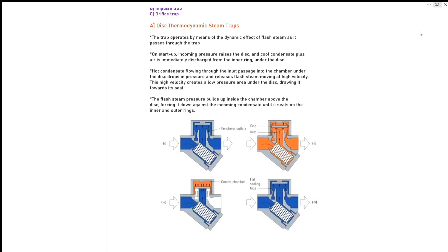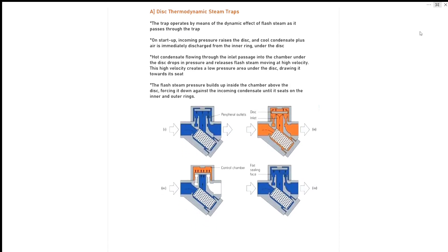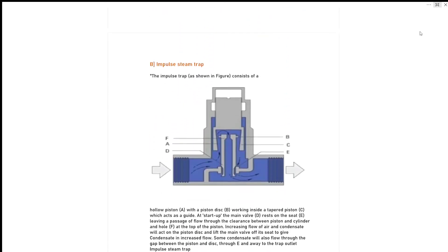Hot condensate flowing through the inlet passage into the chamber under the disc drops in pressure and releases flash steam moving at high velocity. This high velocity creates a low pressure area under the disc, drawing it towards its seat. The flash steam pressure builds up inside the chamber above the disc, forcing it down against the incoming condensate until it sits on the inner and outer rings. You can see the four diagrams here.